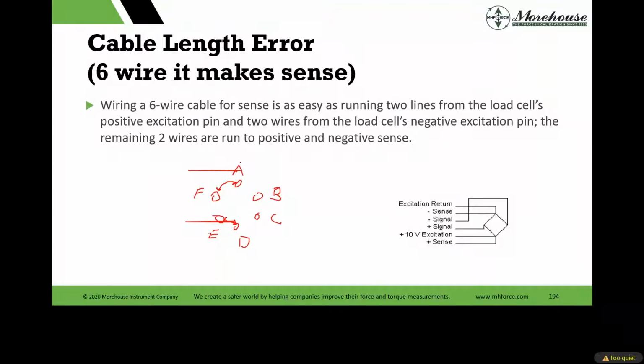What we're basically saying here is that you can run it on the cable side, or you could run it internal. I would not pry a connector off a load cell. They are nitrogen purged and whatnot. So I would just run the cable. Any 4-wire load cell can be used on a 6-wire meter, and you can use the sensing function rather easily by just pairing the positive excitation with positive sense on your cable run, if that makes sense.